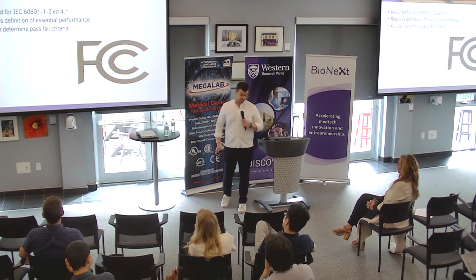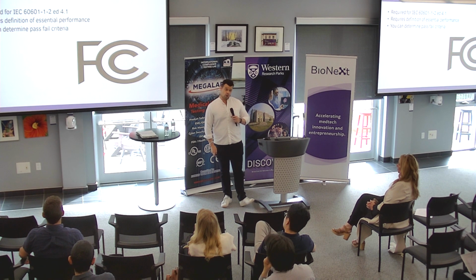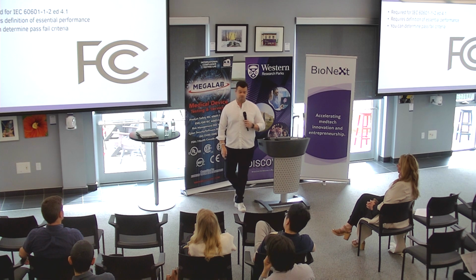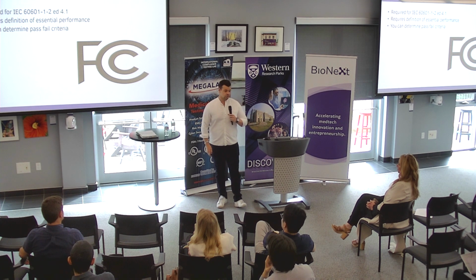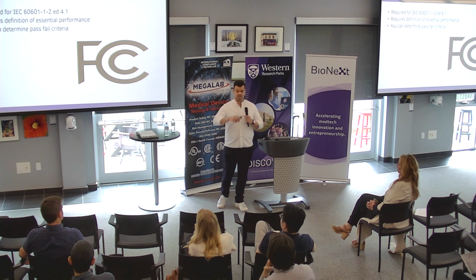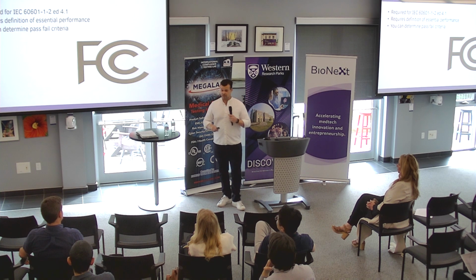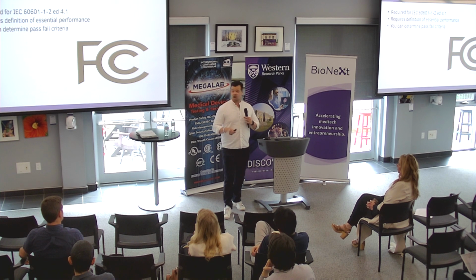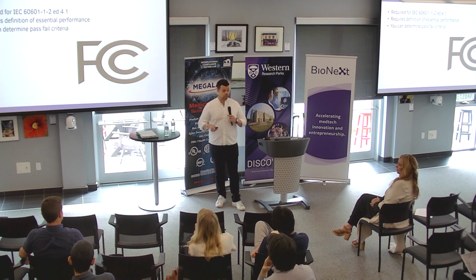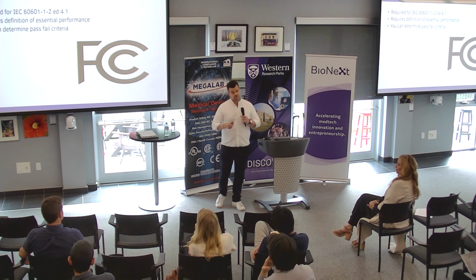For EMC testing for medical devices, one good thing is that you can actually determine the pass-fail criteria. If it was another device, like we call IT equipment, the standard says here's the limit for what's allowed. But with medical devices, there's a little leeway. As long as it doesn't interfere with the essential performance, there's ways to call something a pass.